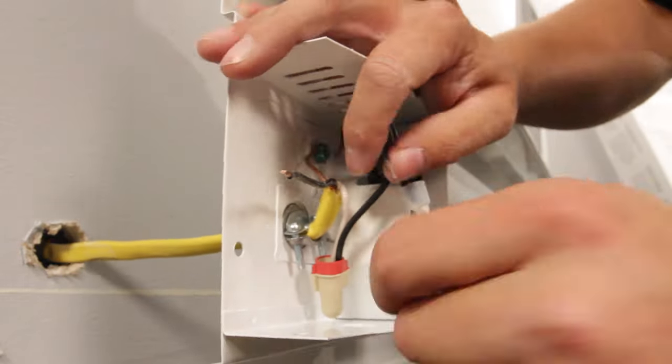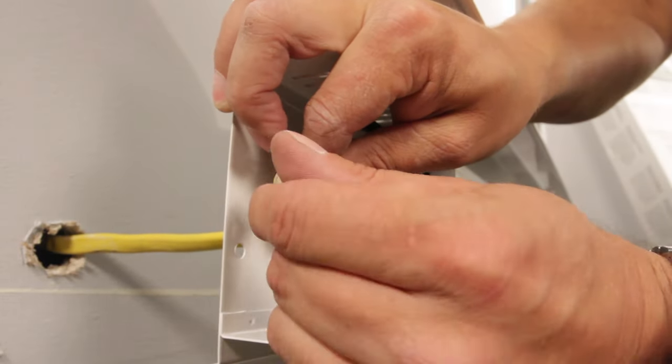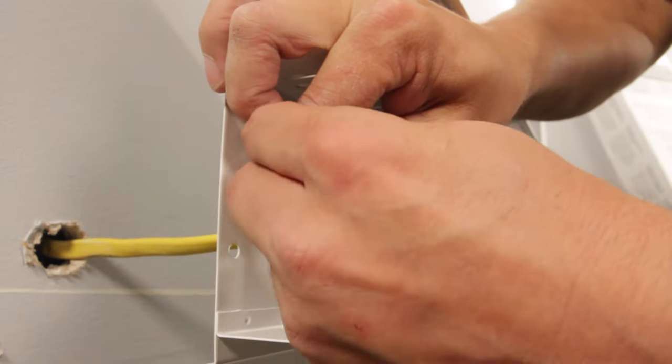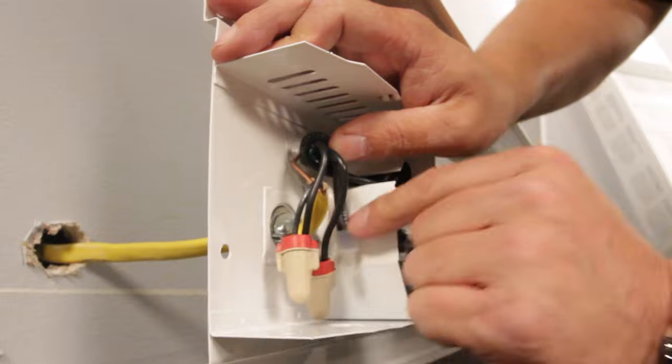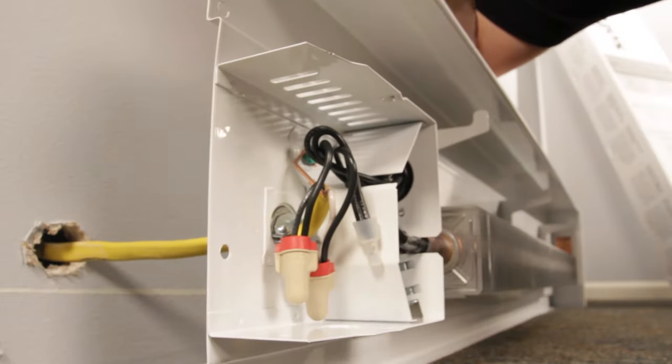Now take the black supply wire coming from the wall and wire it to the remaining black wire coming from the heater. This Cadet soft heat is not polarity sensitive so it doesn't matter which supply wire attaches to the black wires in the heater.